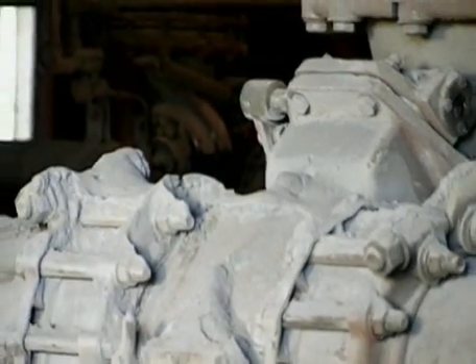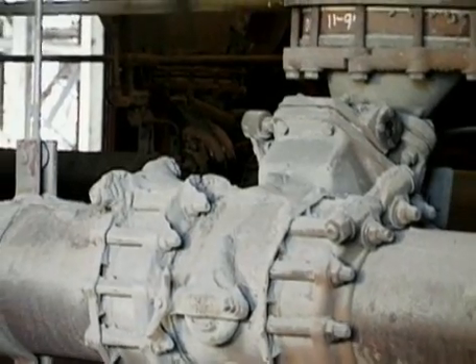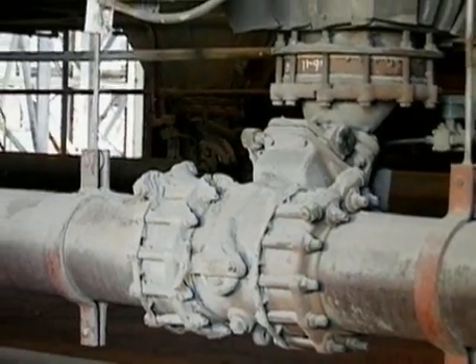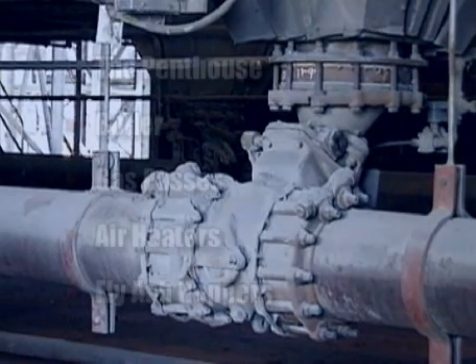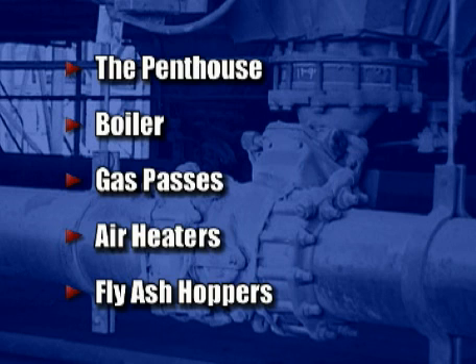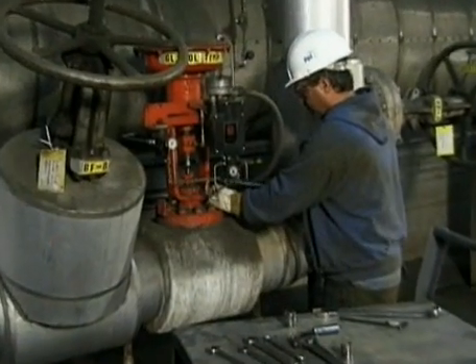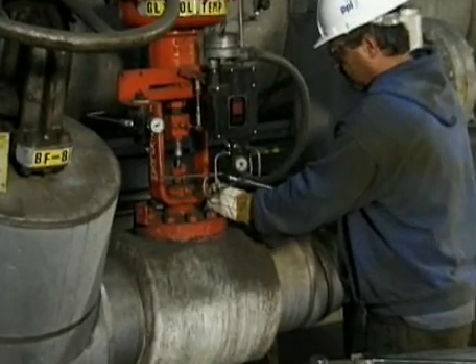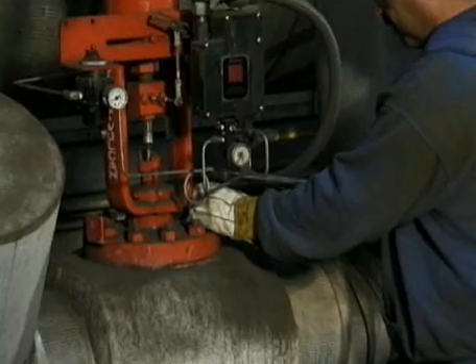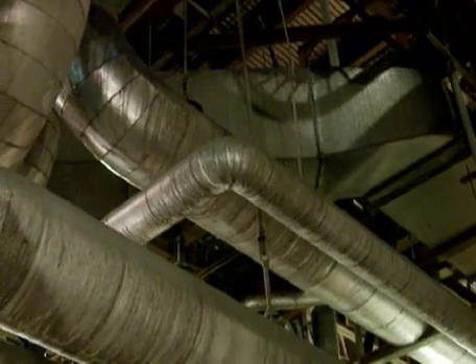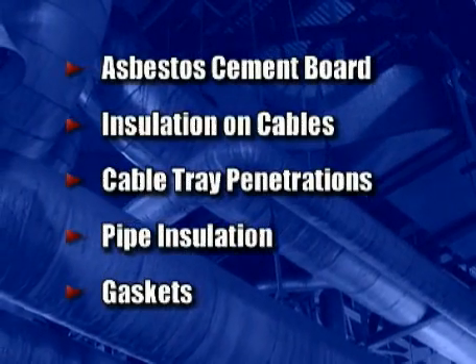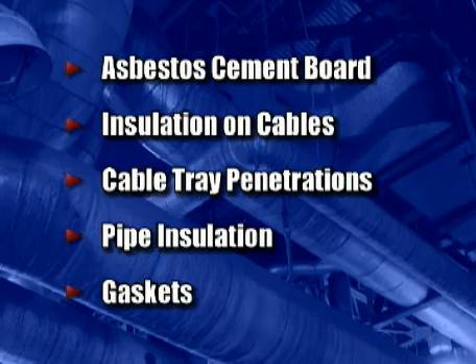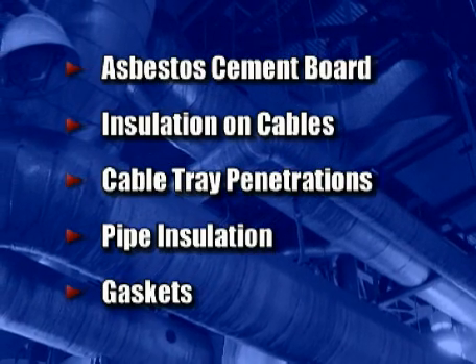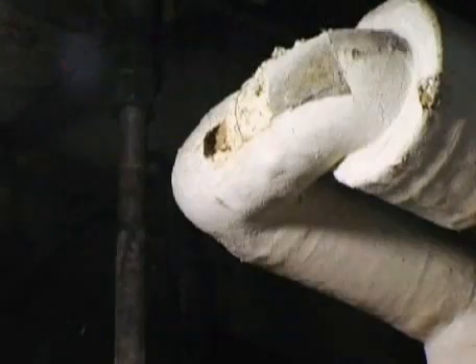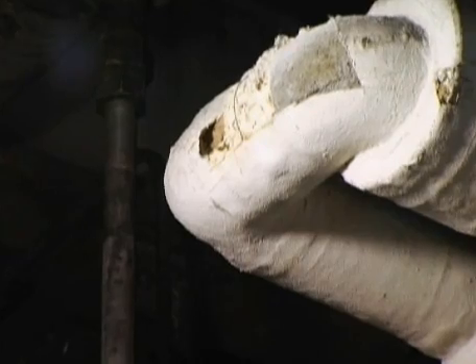Fly ash is another type of dust you should be aware of while working at PPL. Fly ash contains silica and trace amounts of arsenic. Areas that may contain fly ash include the penthouse, boiler, gas passes, air heaters, and fly ash hoppers. Another concern while working in a power plant is asbestos exposure. Asbestos is a naturally occurring fibrous material. In power plants, it has been used for a variety of applications, including asbestos cement board, insulation on cables, cable tray penetrations, pipe insulation, and gaskets. Asbestos can be hazardous if it becomes airborne and friable, and is inhaled.